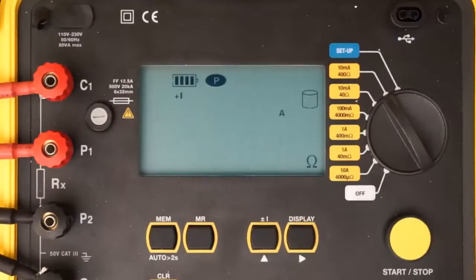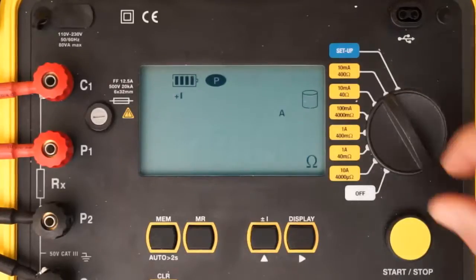When the configuration is set, you are ready to take a resistance measurement. If the resistance you are testing is unknown, we suggest starting with the instrument's highest resistance range and then lowering the range until you obtain meaningful results. In our demonstration, we are using a shunt of known resistance, so we will turn the dial to the 10 amp 4000 micro-ohm setting.